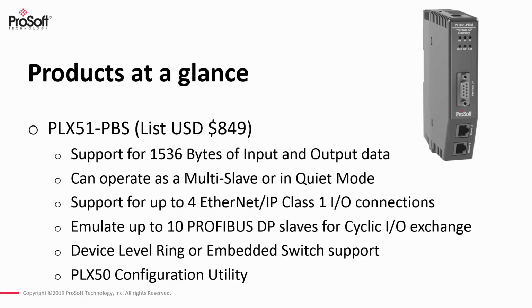But in applications where you know that you're going to be a PROFIBUS DP slave, or you want to operate as a multi-slave, you can go ahead and specify this module, and it's going to give you all the same features and functionality as far as being able to support up to 4 Ethernet IP Class 1 I/O connections, being able to emulate up to 10 Profibus DP slave devices. Also gives you the device level ring or the embedded switch support. And again, it's configured through the PLX50 configuration utility, which is a download off of our website.